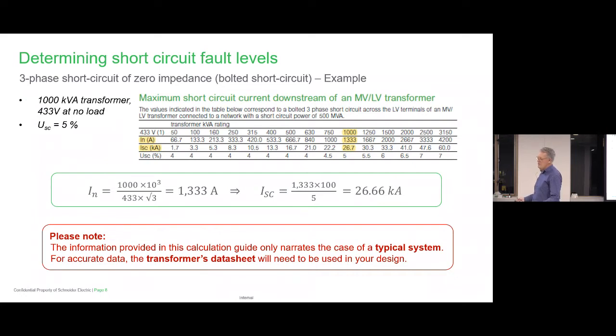And of course, you've got other impedances in there. You've got the cable, you've got the bus bar, all that sort of thing. But we're not taking that into account. We're just saying, look, the transformer is feeding the switchboard, and we're saying the switchboard has got this sitting here. But we know it's going to be less, but so what? Let's start at that point. Because a lot of the protection devices are well above this. They can deal with a lot more than this. So you know that's available from suppliers like ourselves.